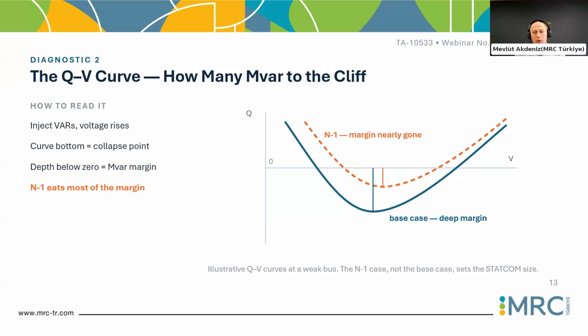Or we may have also some large loads, fluctuating loads, also operating in the grid, localized to a specific region. If there's a heavy industry kind of loads or some huge loads, the reactive power jump may also give some voltage stability issues, and loss of a regional part of the network is also possible. And again, the voltage and reactive power stability margin scanning is represented by the QV curves.